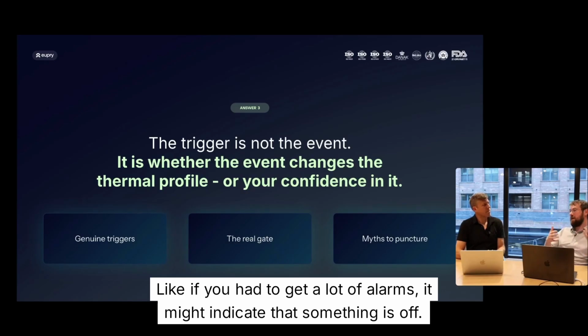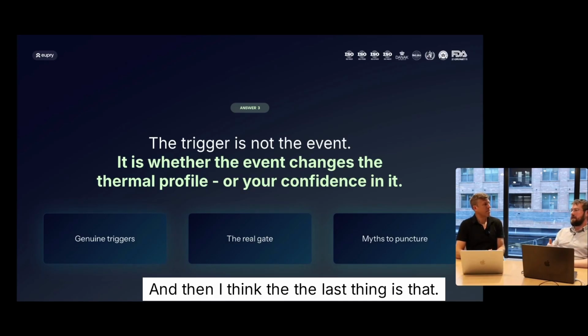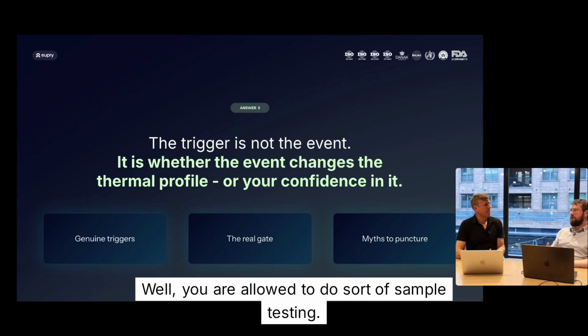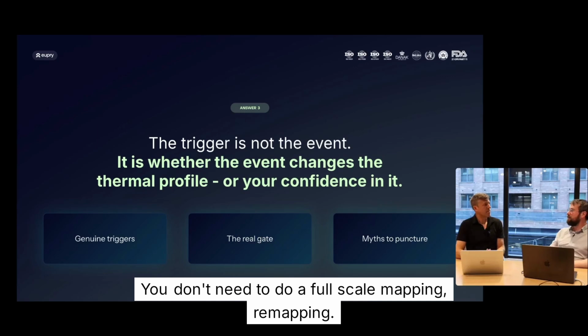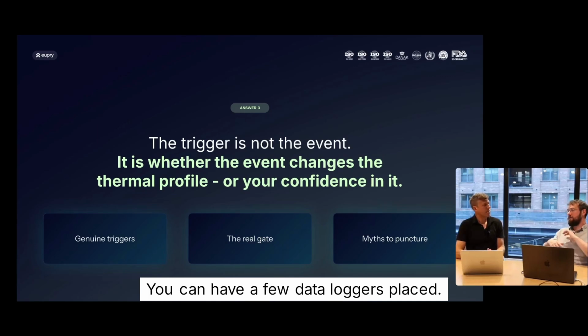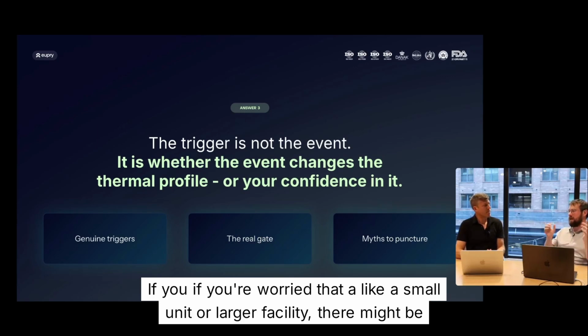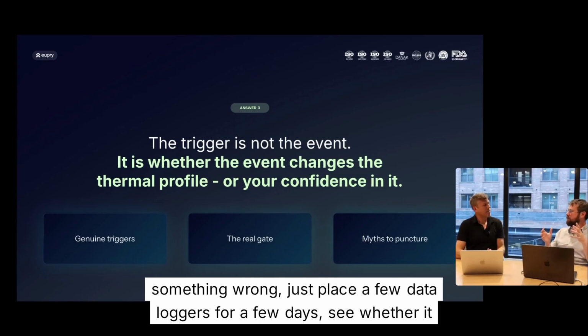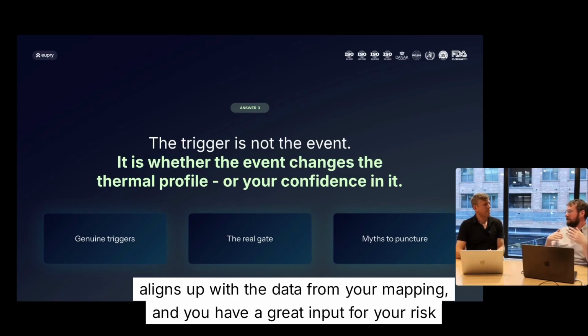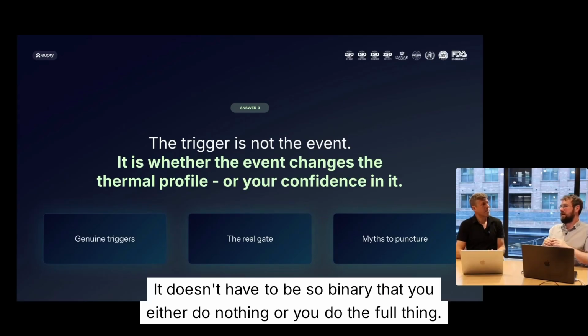If you start to get a lot of alarms, it might indicate that something is off. And then the last thing is that you are allowed to do sample testing. You don't need to do a full-scale remapping. You can have a few data loggers placed. If you're worried that there might be something wrong in a small unit or a larger facility, just place a few data loggers for a few days, see whether it aligns with the data from your mapping, and you have a great input for your risk assessment. It doesn't have to be so binary that you either do nothing or you do the full thing.